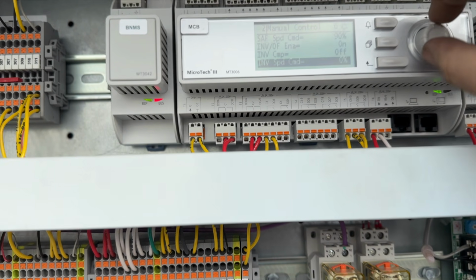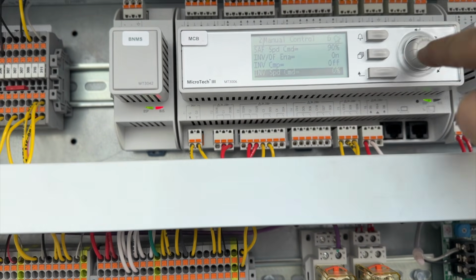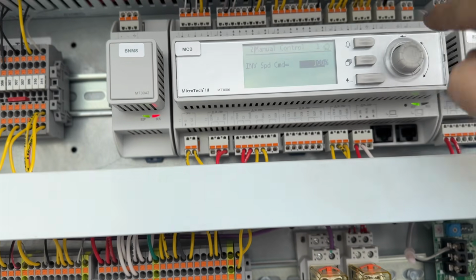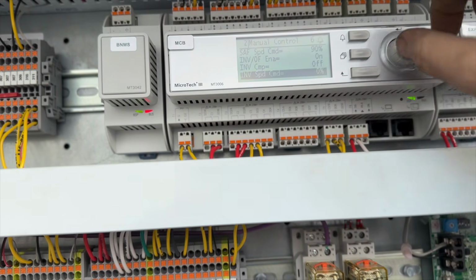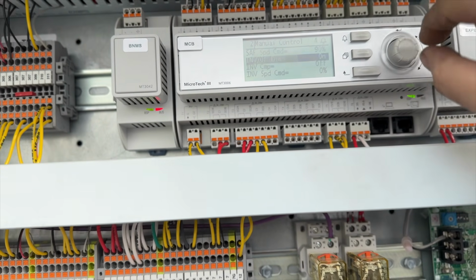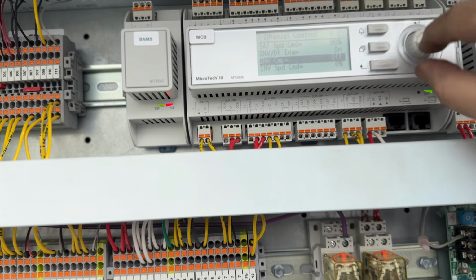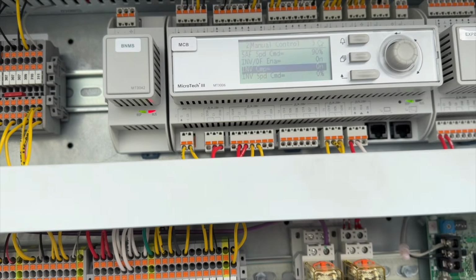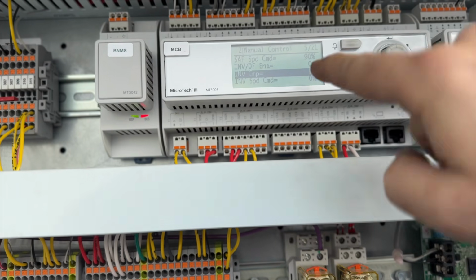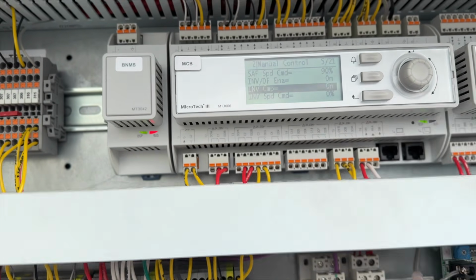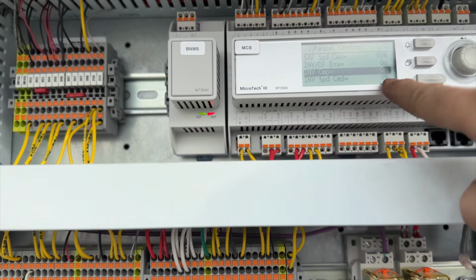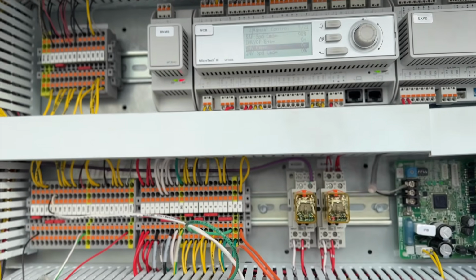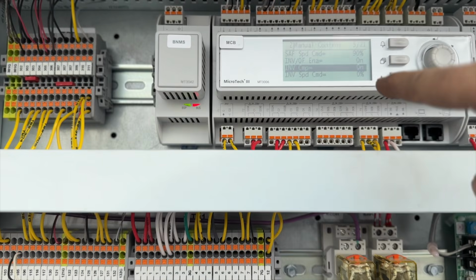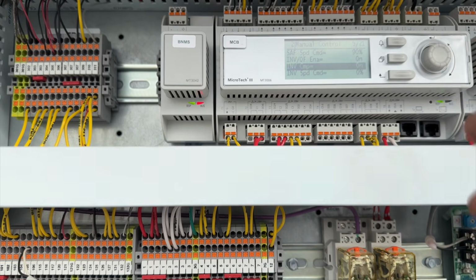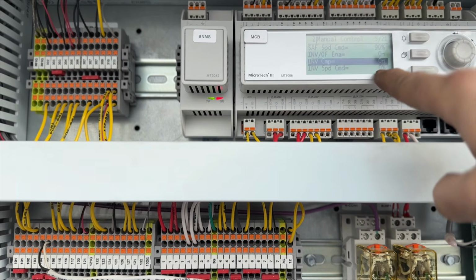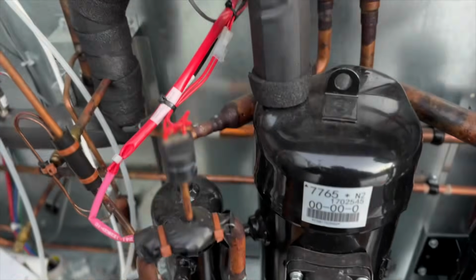Now we need to set the percentage. Keep in mind when you set this, it's gonna immediately go back to 0 because it's monitoring the actual speed. So you've got to set the percentage first, then turn it on. You'll see it drop to 0, but it's actually going to ramp up to 100. Right now it's not doing anything, so it shows 0%. As it kicks on, it takes a while - this will start changing as the compressor ramps up.